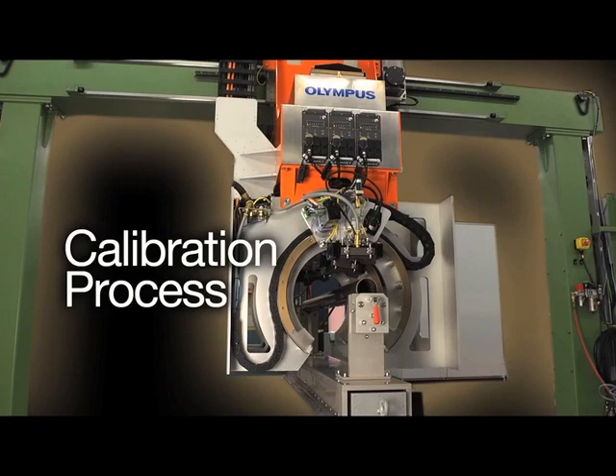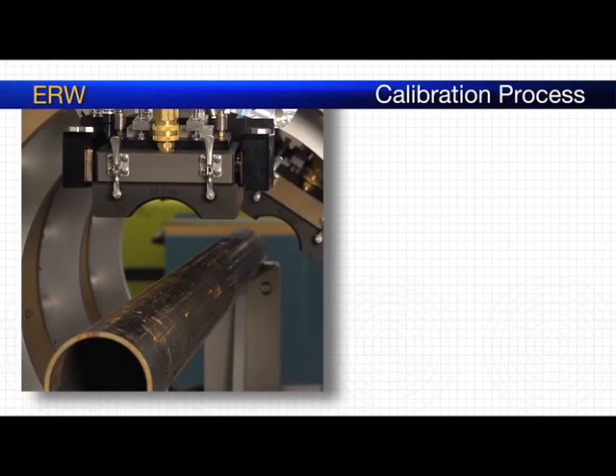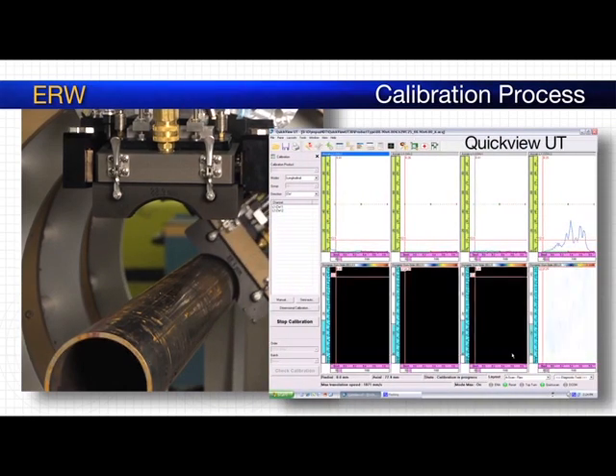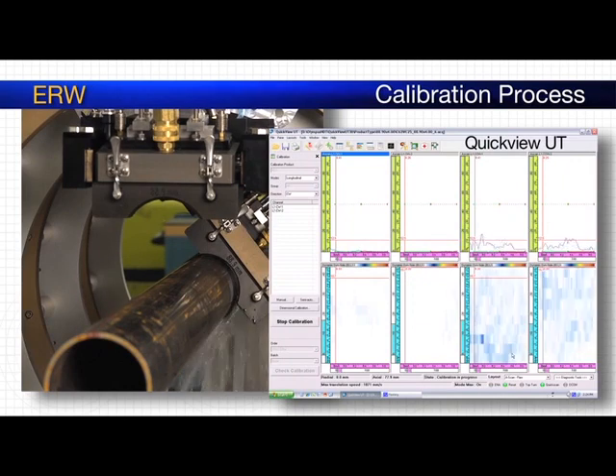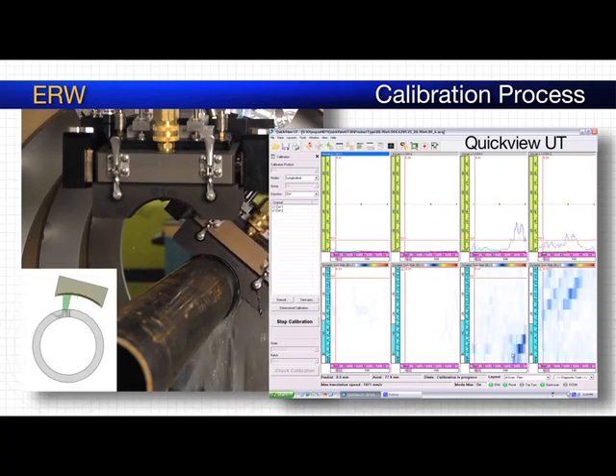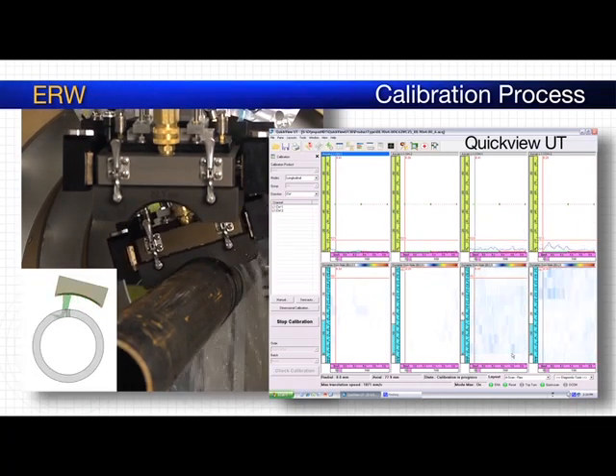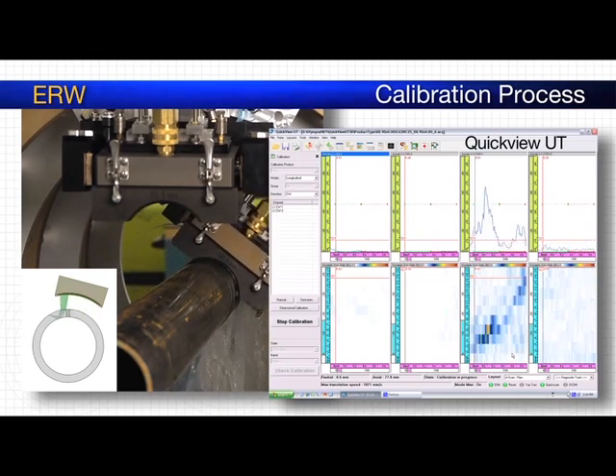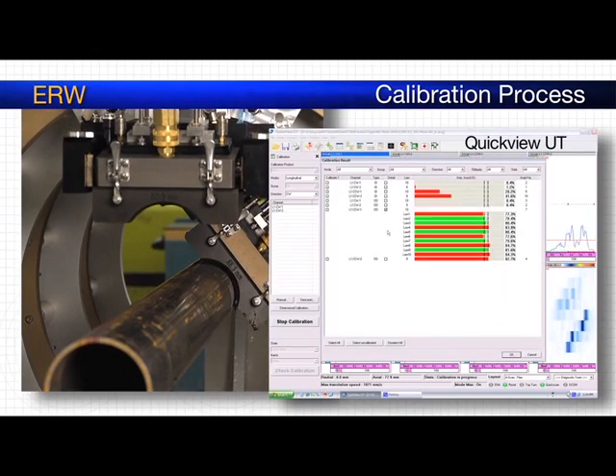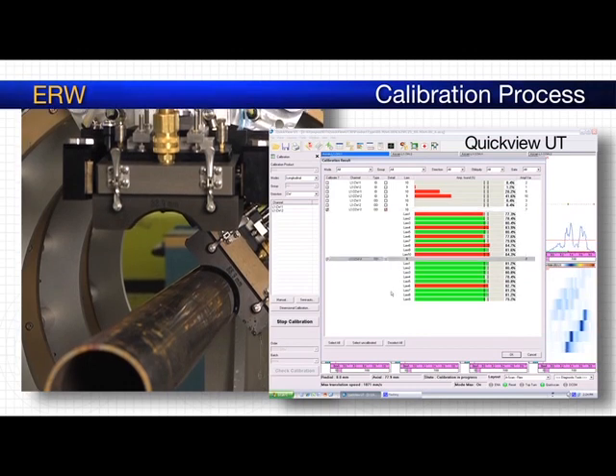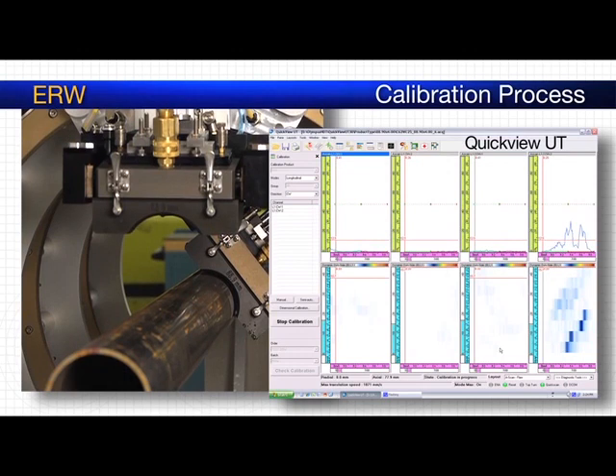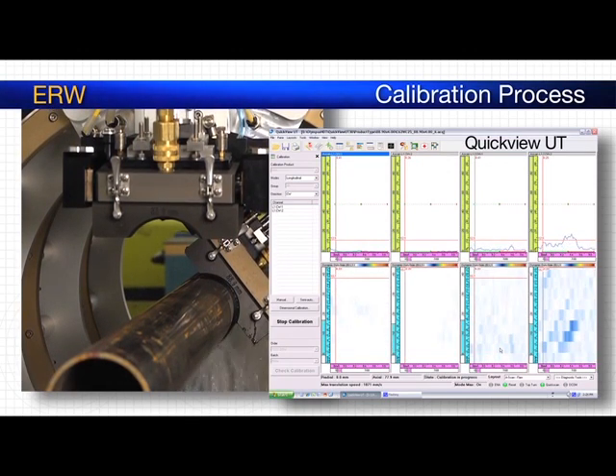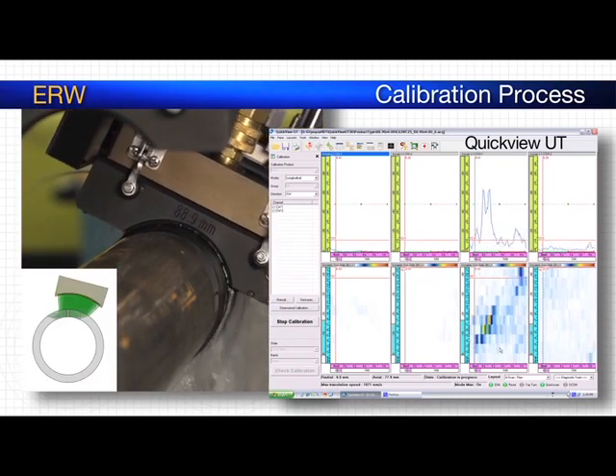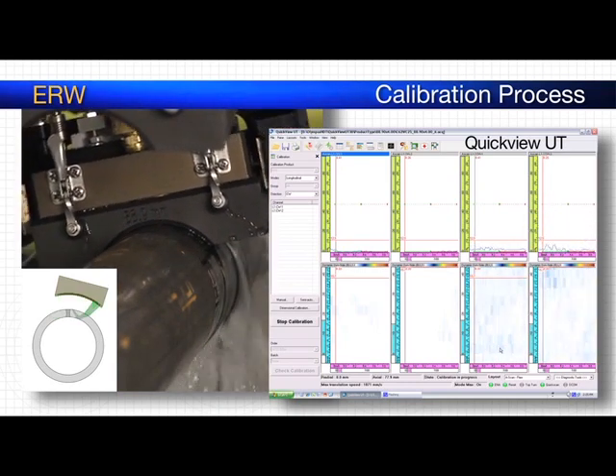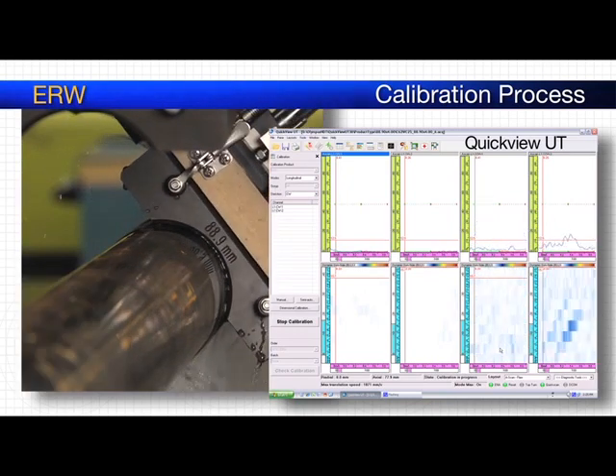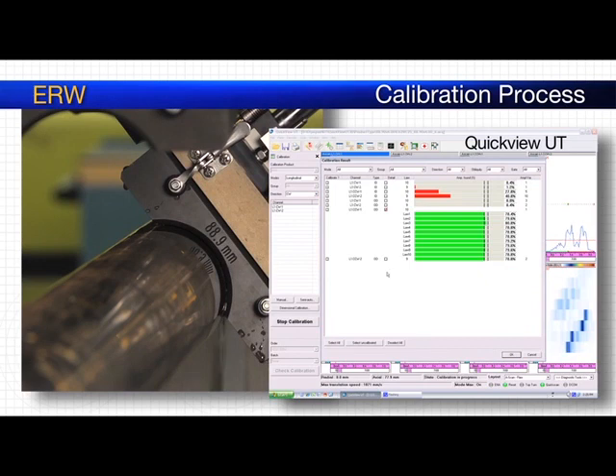During the calibration sequence, we will start by calibrating on a reference defect, with the probe inspecting the first side of the weld. In QuickView, we can see the signal response of every aperture of the phased array probe as it is going over the reference defect. The goal of the calibration is to equalize the response of every aperture to a target of 80% plus or minus 5%. After the first pass, some of the apertures were not at the 80% response level, so we must calibrate all of them by adding or removing the gain level for each aperture. Now, as you can see, after the second pass, the calibration is perfect.